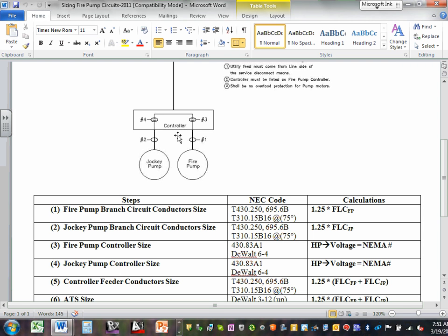So for example, can you just see that? To calculate the branch circuit for the 2 pumps, you take the full load current from the NEC code book. Can you just see that? Multiply by 1.25. Cool? Next, to size the controller, the fire pump controller, for both of them, you take the horsepower and voltage and go to find a NEMA size. Exactly what we did, guys. No difference. Same thing for the jockey pump. You take the horsepower and the voltage, and from the DeWalt book, you can go find a NEMA size.